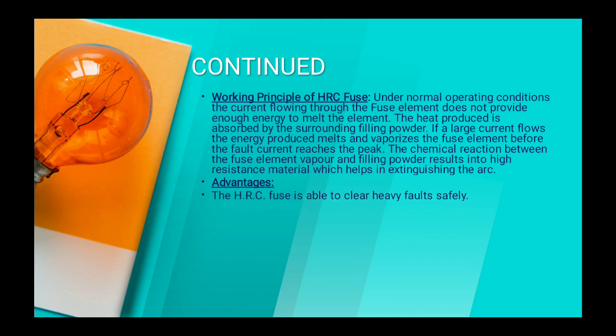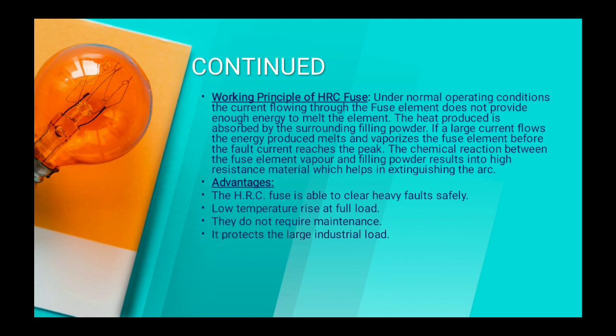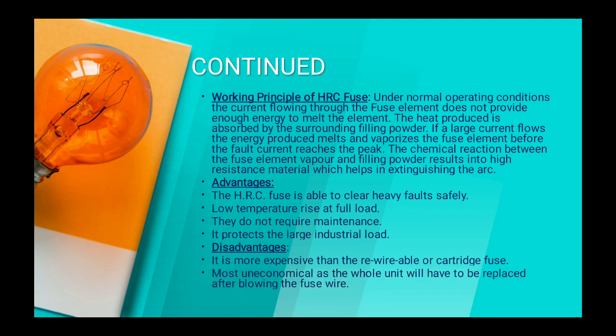Now the advantages. The HRC fuse is able to clear heavy fault safely. It is used for medium voltage protection or overload protection of motors. Low temperature rise at full load. They do not require maintenance because there is a heat absorbing medium. It protects large industrial loads. Disadvantages: it is more expensive than rewireable or cartridge fuse because it cannot be rewired. You have to replace it after one operation. Most uneconomical as the whole unit has to be replaced after blowing the fuse wire.